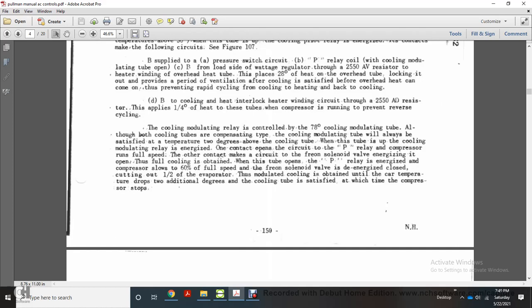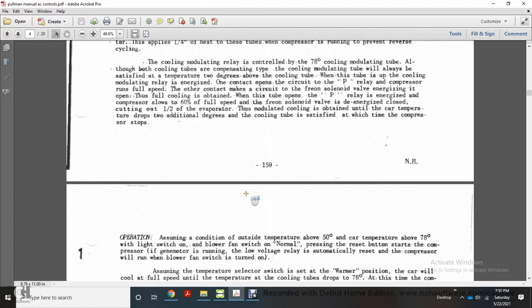When the cooling modulating relay is energized, one contact opens the circuit to the P relay so the compressor runs at full speed, while the other contact energizes the freon solenoid valve to open for full cooling. When the tube opens the P relay, the compressor slows to 60% of full speed and the freon solenoid valve is de-energized and closed, cutting out half the evaporator for modulating cooling. As the car temperature drops two additional degrees, cooling is satisfied and the compressor stops.